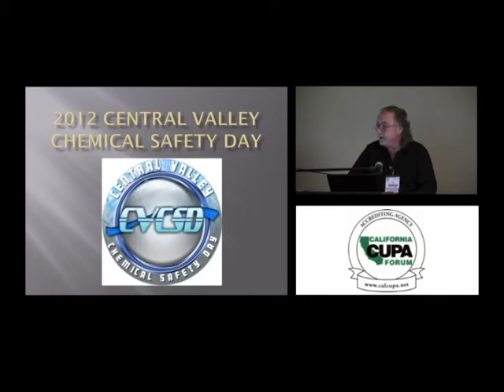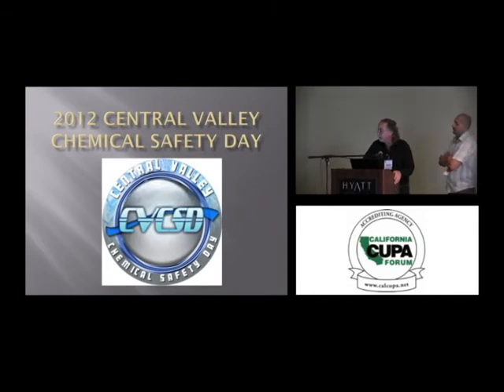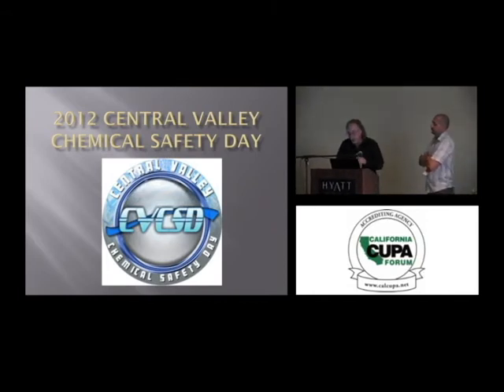But they should have legible nameplates, and in this day and age on newer facilities, the backup U1 form, which basically is the birth certificate for the vessel on site. This happens to be a pressure relief valve that's on top of a nurse tank, just relieving directly to atmosphere about 3-4 feet off the ground.